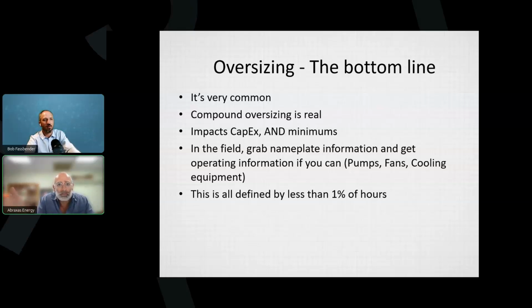I'm just modeling the system. Is there an oversizing problem here? I'm just modeling what I see. It is 100 horsepower. I have the GPM label. I'm not going to be able to measure the GPM, let's say. I just don't have a flow meter, so I just take the GPM from the label on the pump. Is that a problem to do that?